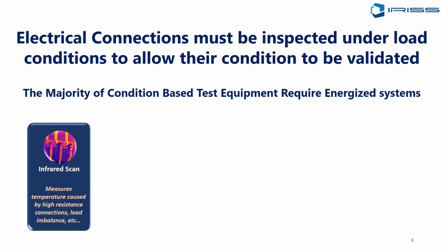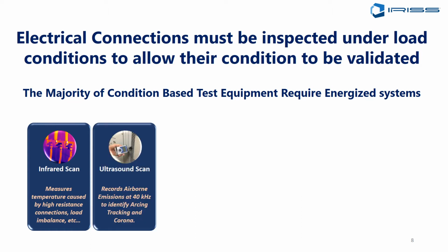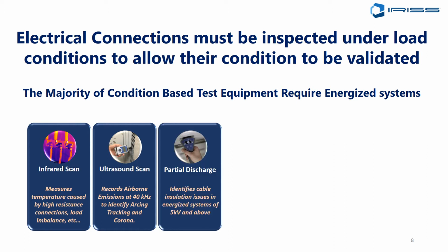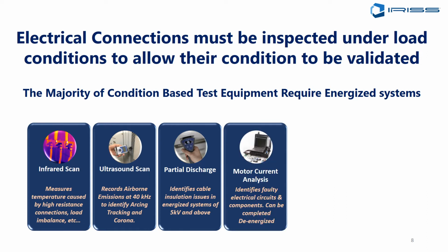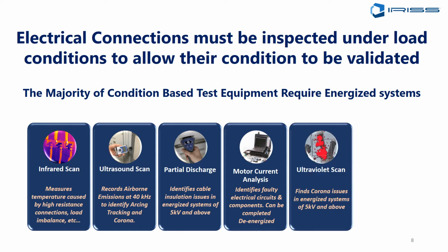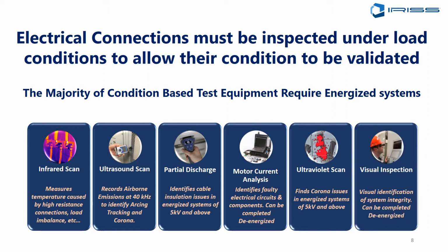What we tend to look at in condition monitoring is infrared and ultrasound. With ultrasound, we're looking for 40 kilohertz emissions. Partial discharge is typically over 4.5-5 kV, but we can do PD inspections. Motor current analysis can be done energized and de-energized. Ultraviolet is being used extensively now, especially in the power generation fields, again for identifying corona over 5 kV. And the most important thing is visual inspection. So this is what we do.